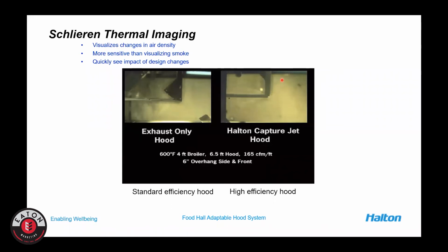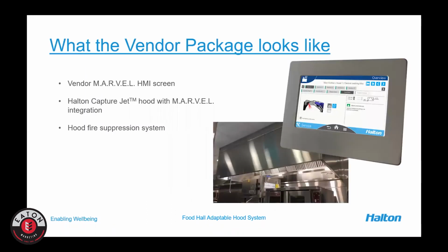Here we have the ability, with a higher efficiency hood, to do a better job of capturing and containing and keeping that heat within the hood. This hood can do the same amount of work, but without the perimeter jet system that allows us to lower that airflow, we would have to increase airflows on the exhaust plenum to create a greater suction pressure to achieve those same results. So the vendor package, you would typically have the hood itself.